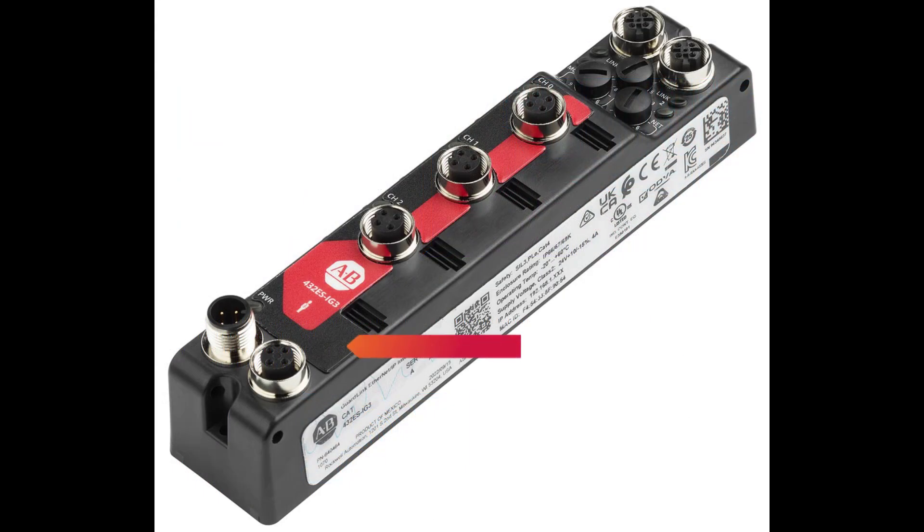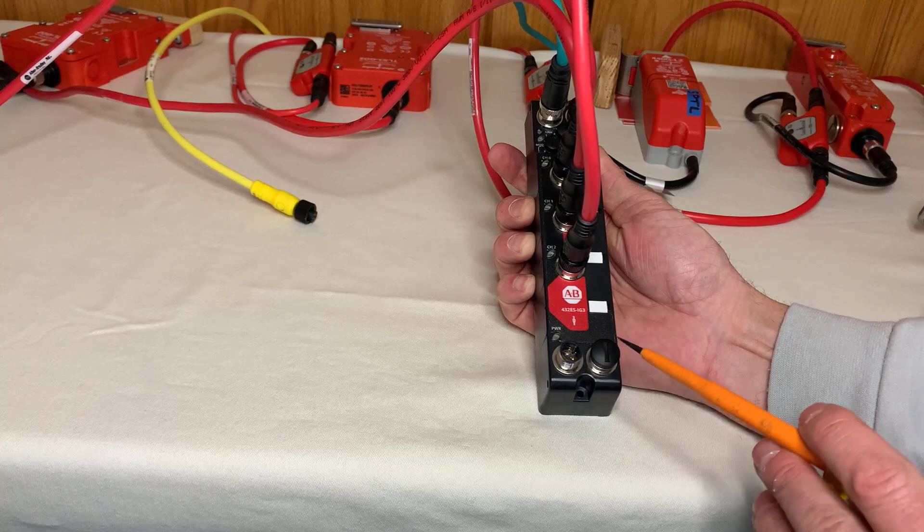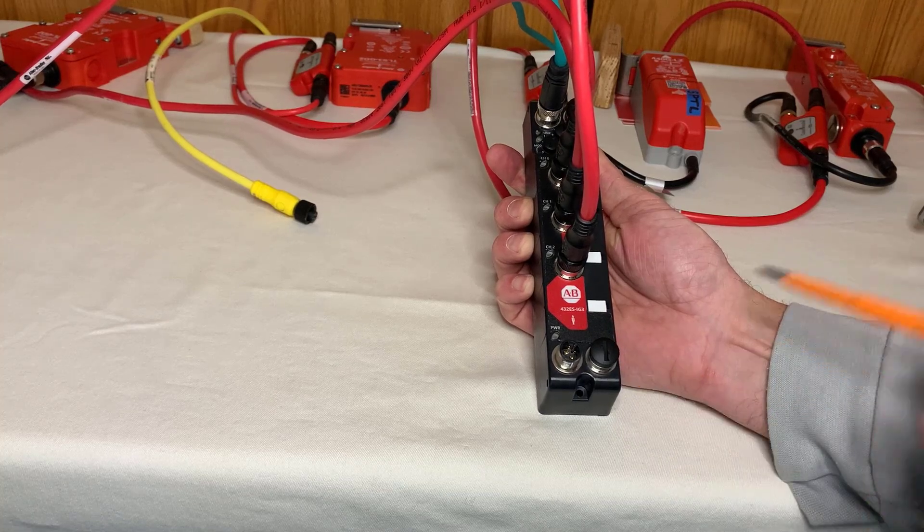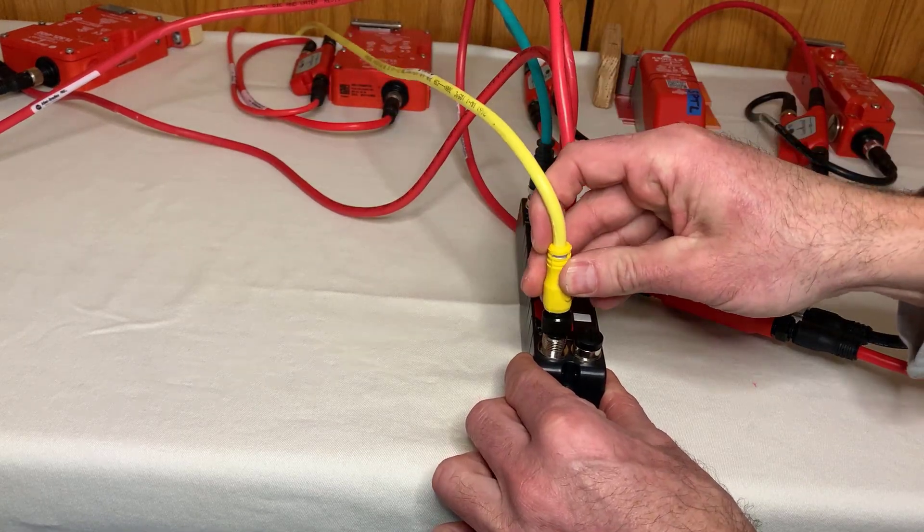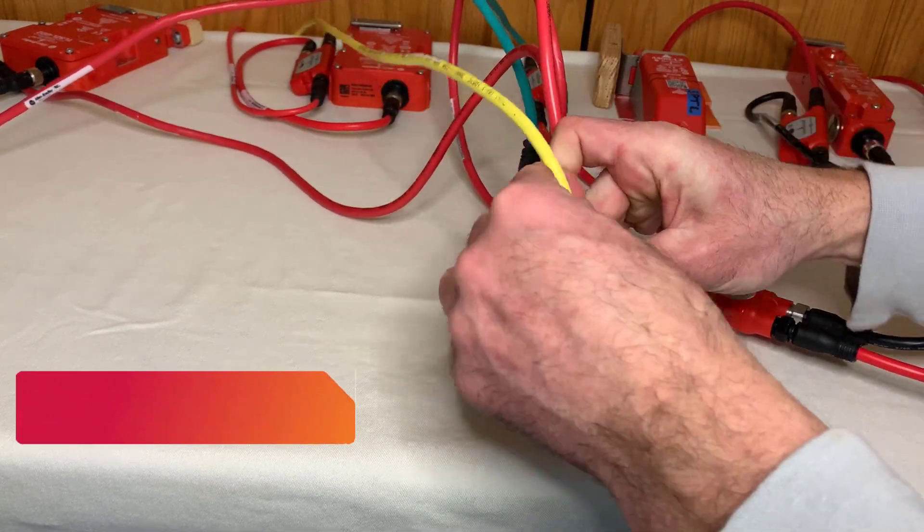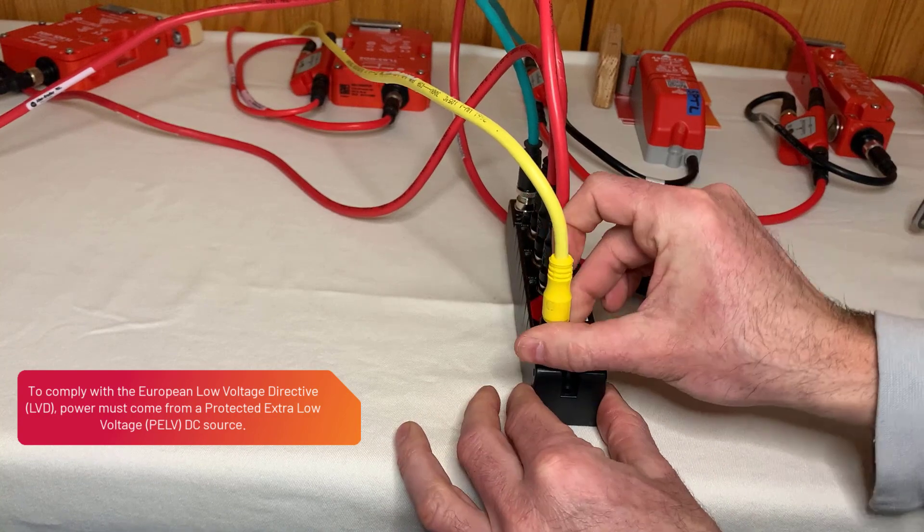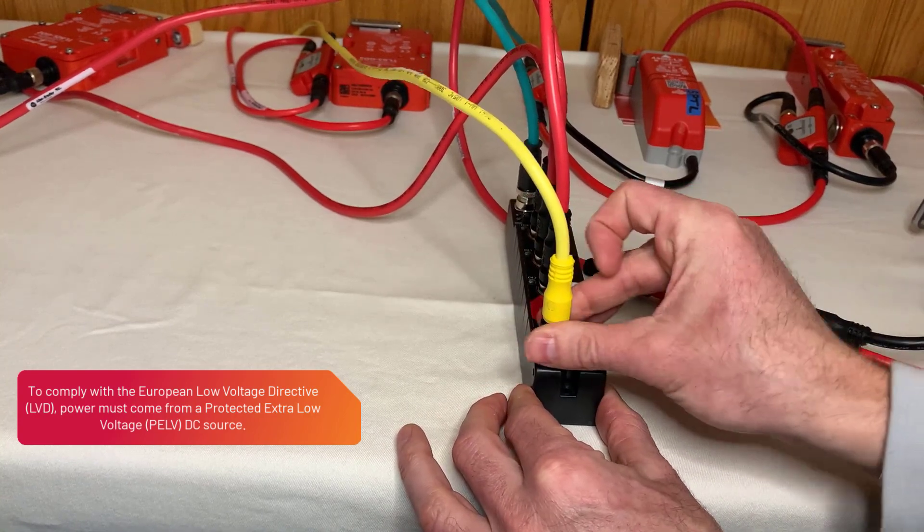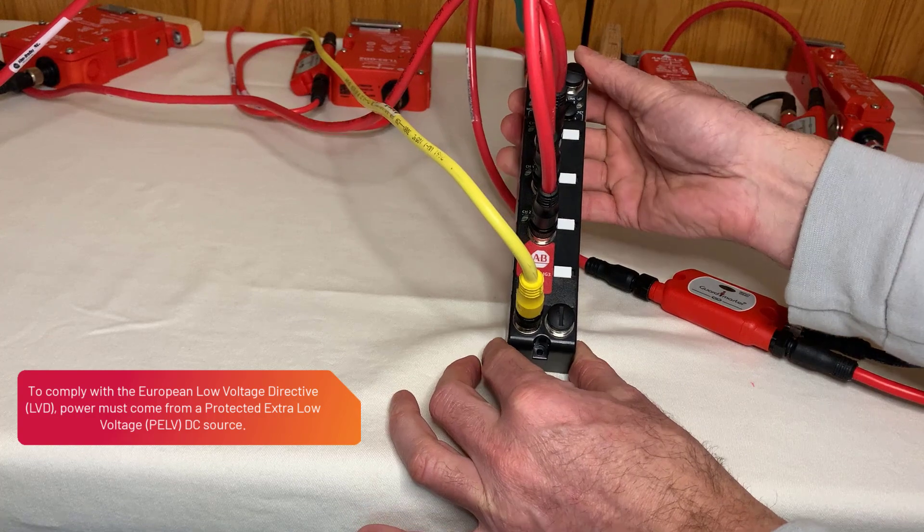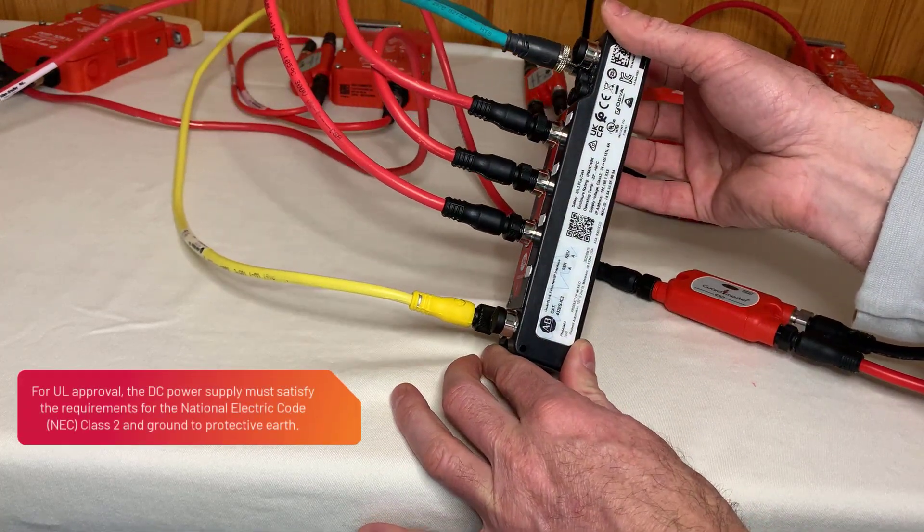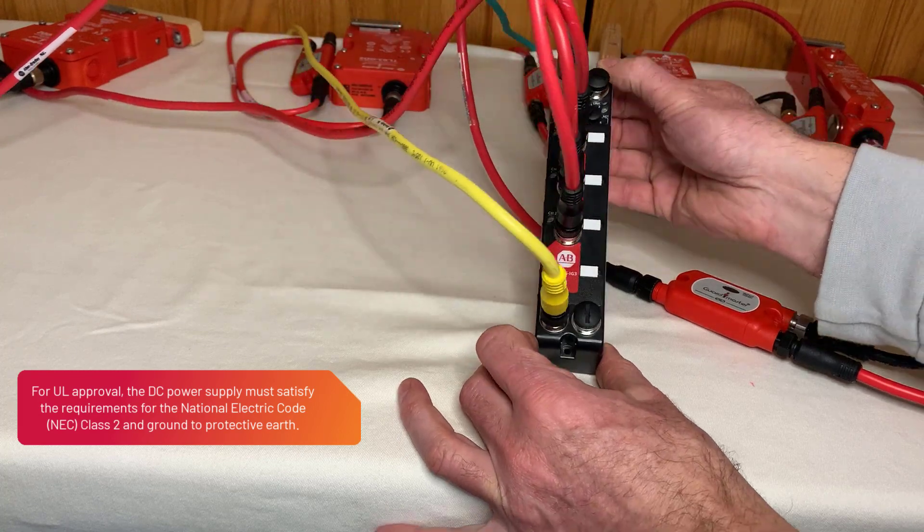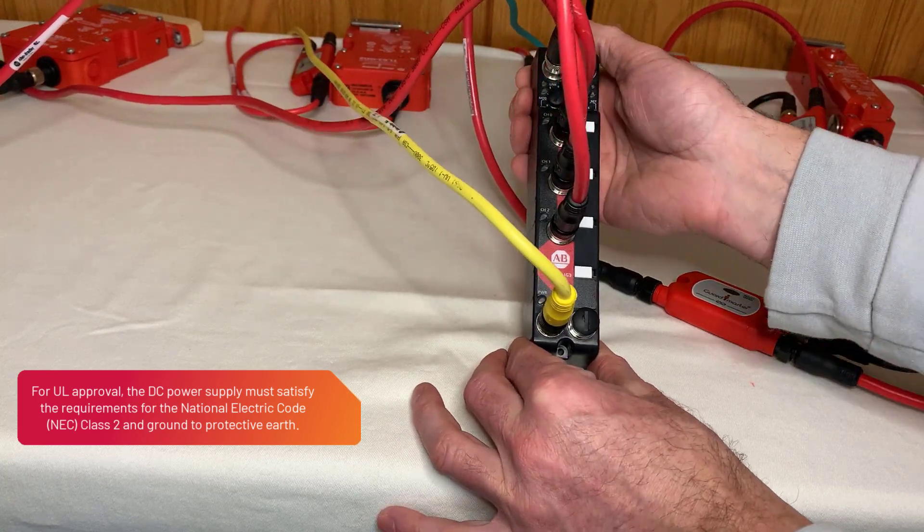The final two plugs on the bottom of the module are for 24-volt DC power. DC power in and DC power out to the next device. Here in the lab, I use whatever 24-volt DC that is available. But please note that to comply with the European Low Voltage Directive, Protective Extra Low Voltage or PELV power supply is required. And to meet Underwriters Laboratory or UL requirements, a National Electrical Code Class 2 power supply is required.